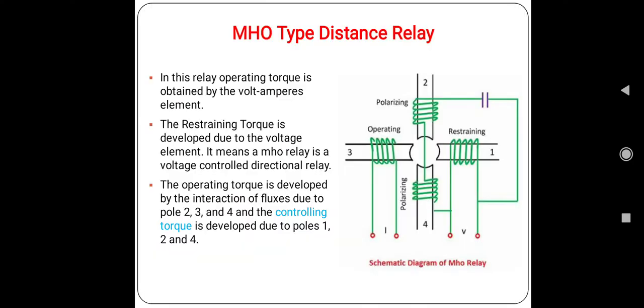The Mho relay is a very high speed relay and is also known as admittance relay. It is also sometimes called an angle impedance relay. In this relay, operating torque is obtained by the volt-ampere element and the restraining torque is developed due to the voltage element. It means a Mho relay is a voltage restrained directional relay.